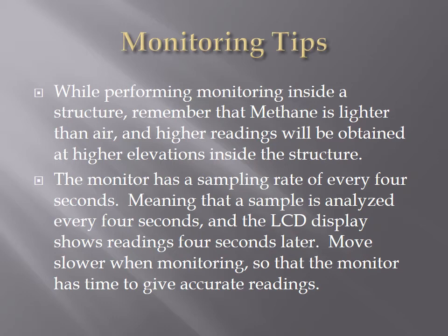The monitor also has a sampling rate of every 4 seconds. So let me talk about that for a moment. What that means is that a sample is going to be drawn into the monitor and analyzed every 4 seconds, and the LCD display screen will show what that reading is approximately 4 seconds later. So what does that mean to you as the user of this instrument? What that means is when you're monitoring, you need to slow down. Don't walk at a normal pace through a structure or in any environment that you're monitoring. You have to give time for the monitor to draw the air sample in, analyze it, and give you a reading. Now that might dictate that you're in an area longer, but you're doing it safer, and that is key.